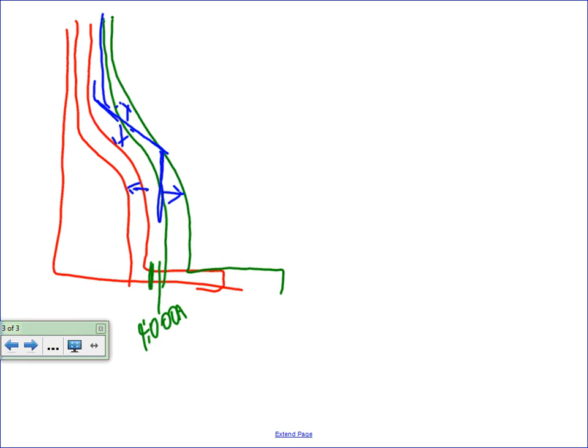And then on our larger solid state breakers, we have the ability to turn off the instantaneous. But even if we turn off the instantaneous, there's still what they call a selective override built into every breaker, and that's the amount of fault current that breaker could probably withstand without blowing off the wall. Okay, and that might be 18,000 amps, it might be 65,000 amps, depending on the type of breaker and the design. So we turn off the instantaneous, and we are moving this curve way over here to whatever that override on the breaker is, on our frame that's 35K. So now that 400 amp breaker, we're fully coordinated with that downstream breaker.